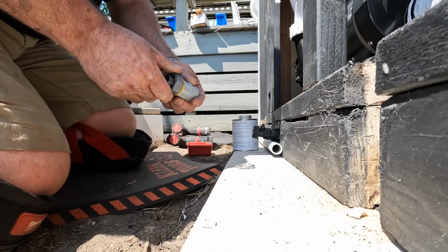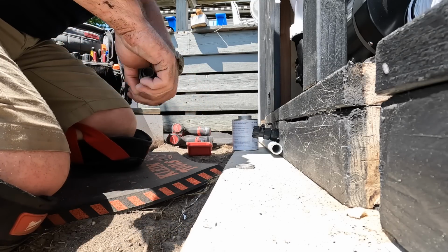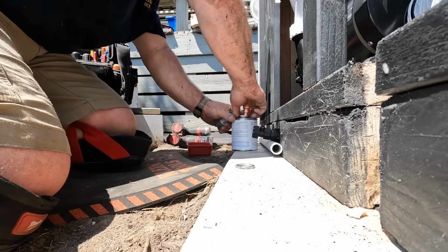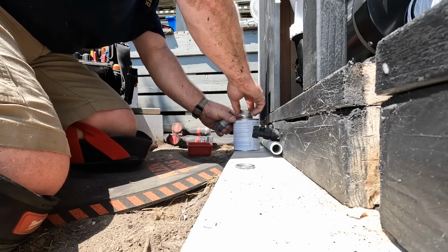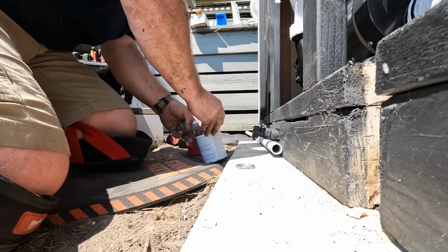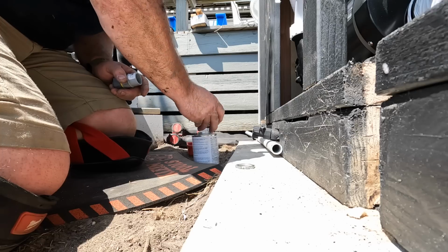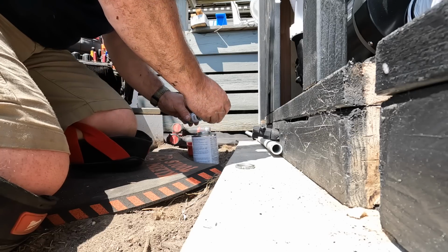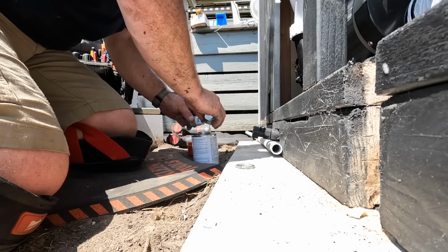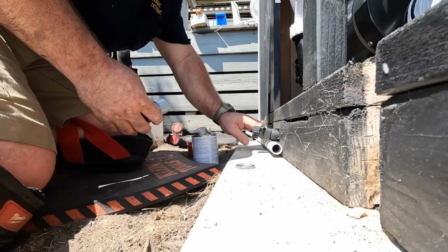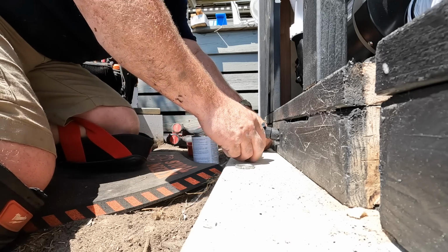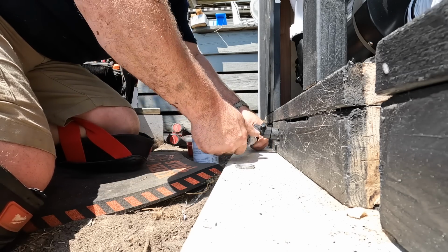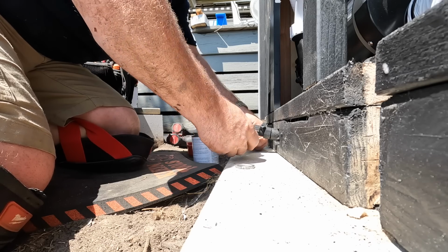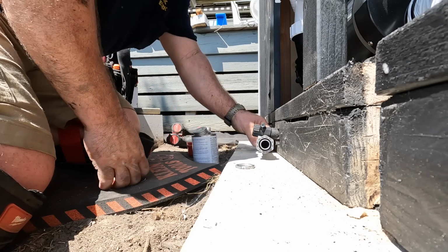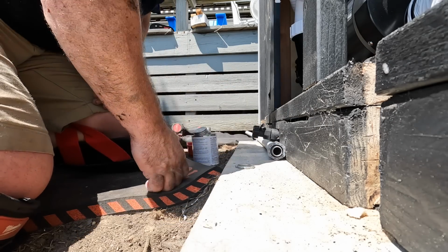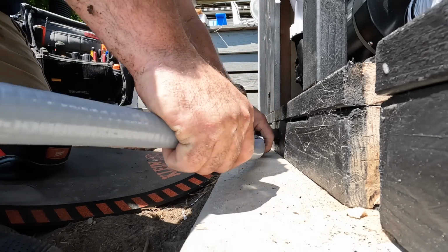So this is where I transition from the rigid PVC to the flexible PVC. I'm using what's known as a 3/4 inch female adapter, which is a coupling on one end and a threaded coupling on the other end, which I attach the flexible straight connector to, and therefore you could transition from the rigid PVC to the flexible PVC. That's what I'm doing here. And then I'll come back with the flex and attach it right to that straight connector, as you see here.